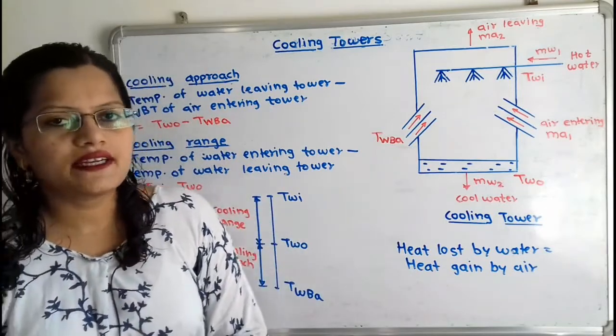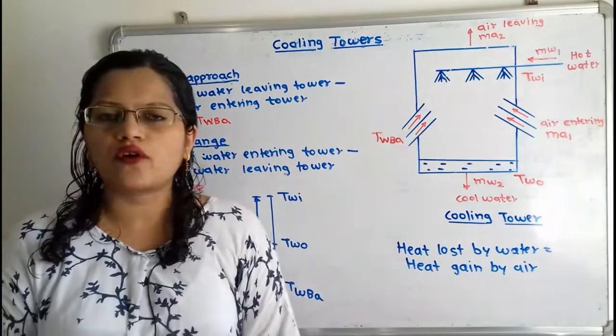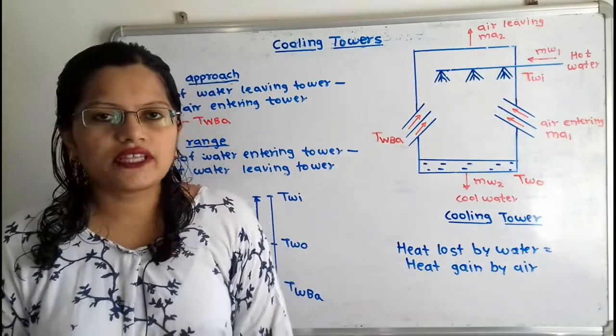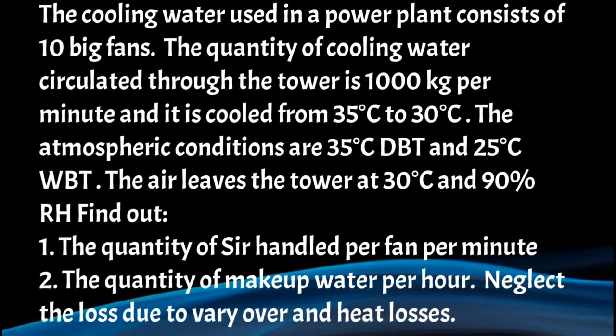Now we will understand the heat transfer process taking place inside the cooling tower with the help of a psychrometric chart. For that we will solve one example. The cooling water used in a power plant consists of 10 big fans. The quantity of cooling water circulated through the tower is 1000 kg per minute and it is cooled from 35°C to 30°C. The atmospheric conditions are 35°C dry bulb temperature and 25°C wet bulb temperature. The air leaves the tower at 30°C and 90% relative humidity. Find: (1) the quantity of air handled per fan per minute, (2) the quantity of makeup water per hour. Neglect losses due to carryover and heat losses.